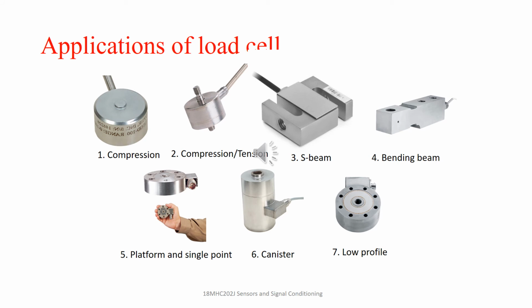There are various types of load cells available which must be rightly chosen for our application. First type is the compression load cell. This has an integral button design. They are ideal for mounting and provide long-term stability. Second type is the compression or tension load cell. So these are used for applications where the load may go from tension to compression and vice versa. Because of the threaded end, it is easy for installation. This is ideal for space restricted environments.